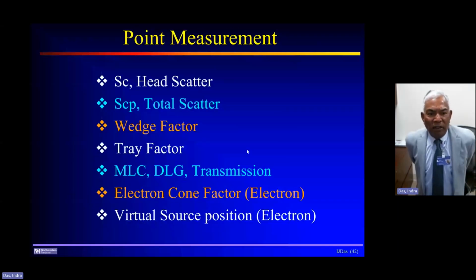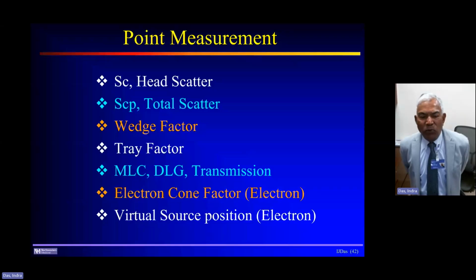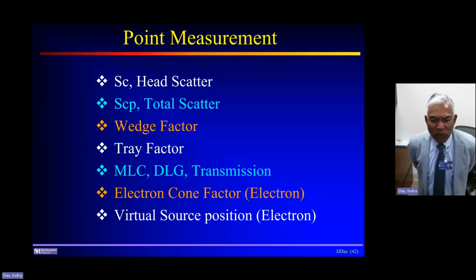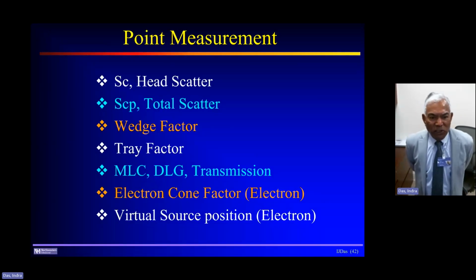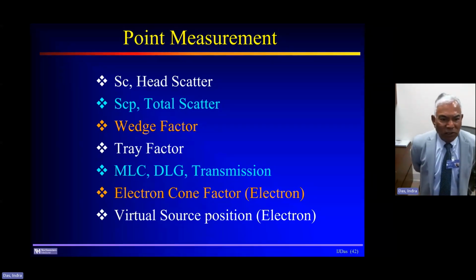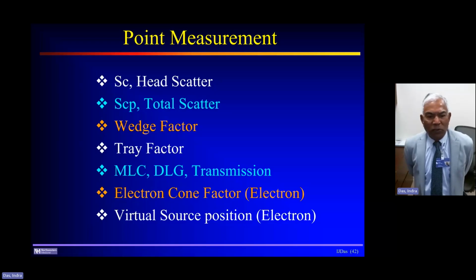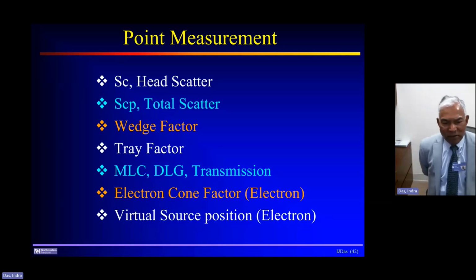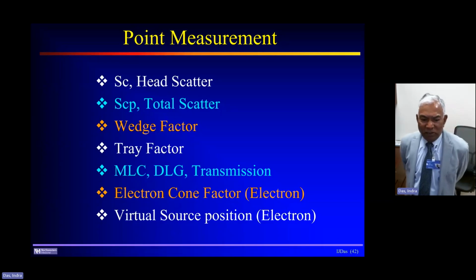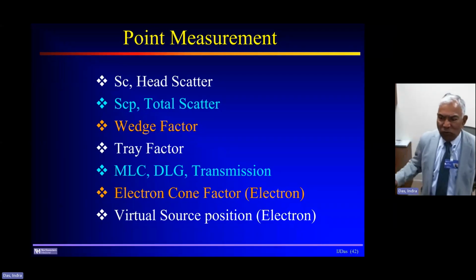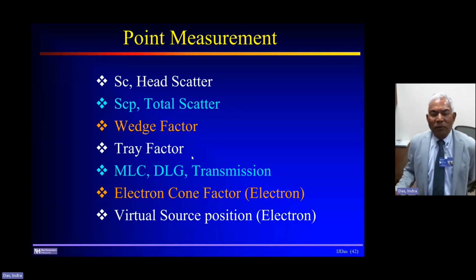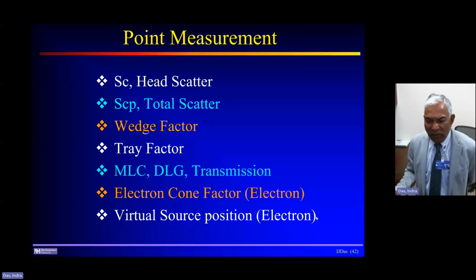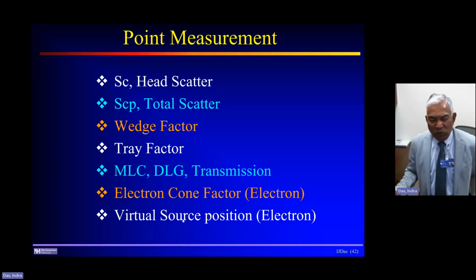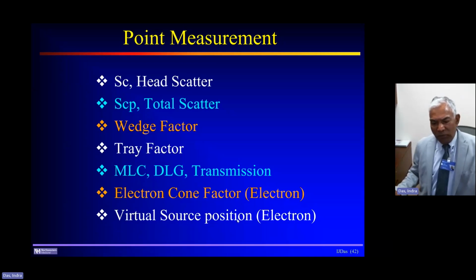The head scatter, these are all simple bread and butter things. In the old days we used to do that, and we still do that, but there is still an art to measuring head scatter, total scatter, wedge factors, tray factors, MLC, DLG, transmissions, electron cone factor, and virtual source positions. There are a lot of things you still have to commission. For some treatment planning systems you don't need the virtual source positions because they are Monte Carlo based, but validations may still be required.